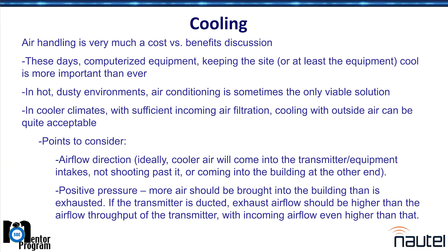What they did: the transmitters at the time had about a 2,500 cubic feet per minute airflow. They brought 4,000 CFM into the building through a big old wall of filters, took 3,000 CFM out of the building, directed all the air through the transmitter, and positively pressurized the whole works. At that point, maintenance becomes swapping out air filters.